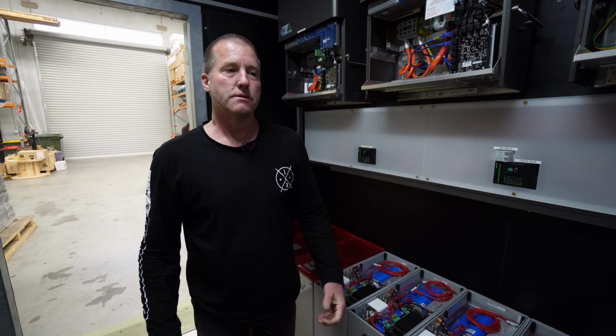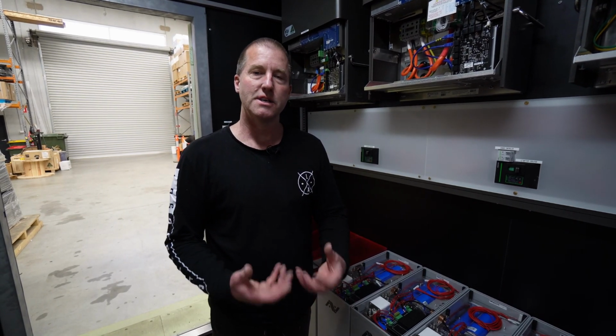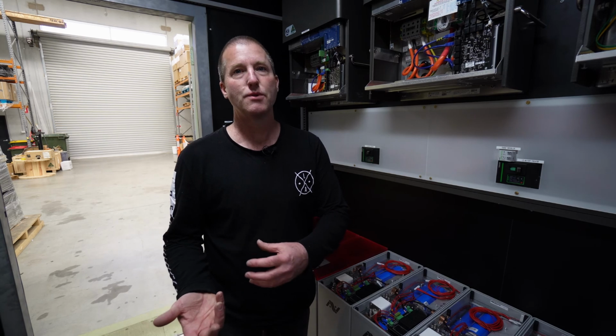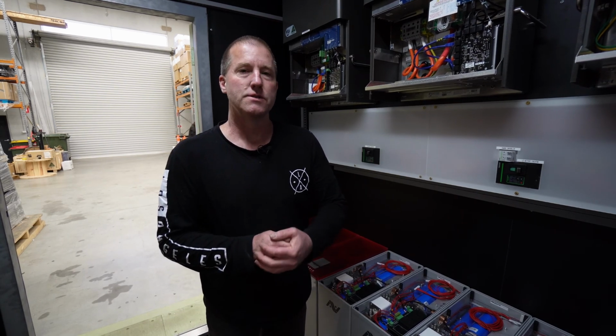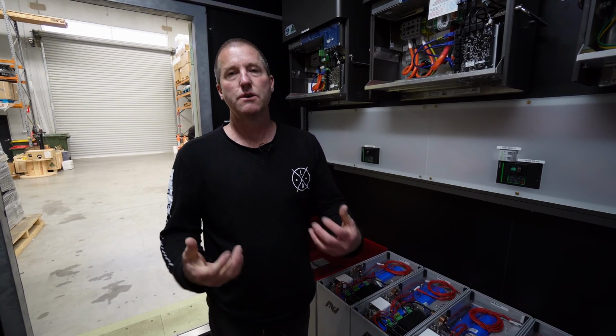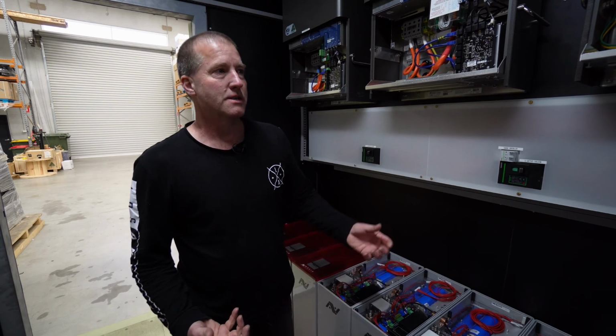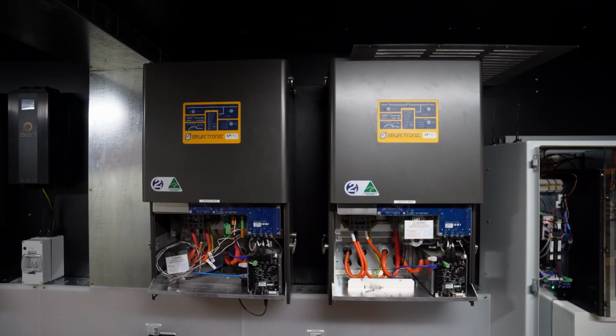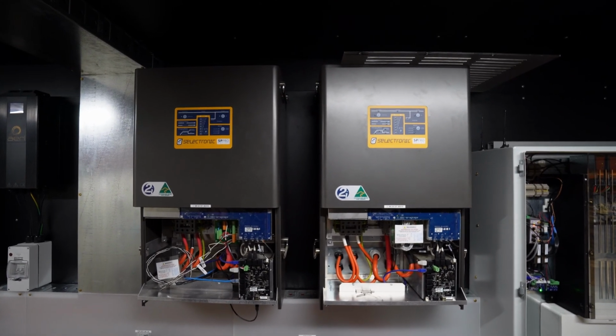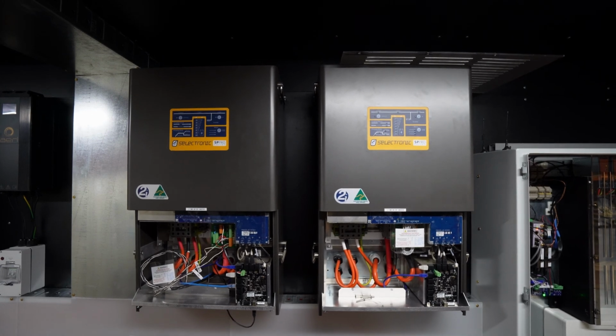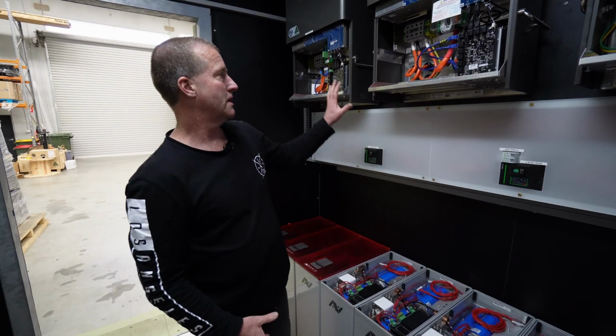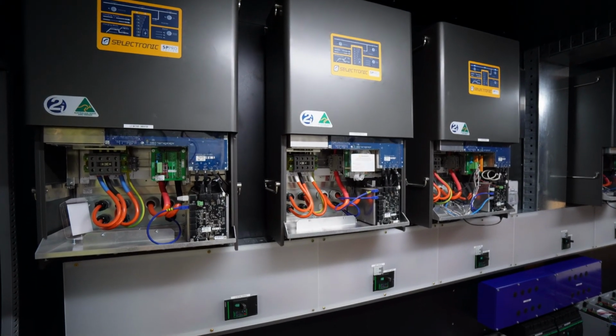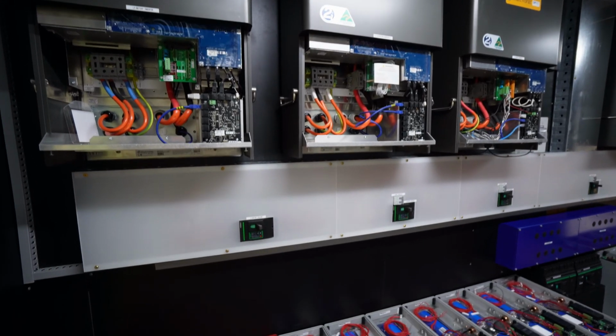So we said, why don't we design a system to bring in the single-phase power and convert it to DC, then produce a three-phase supply for you. That'll also give us the ability to add a lot more solar, because we're off the grid. So we designed a system where we bring in two inverters off the SWER line, produce a DC bus, and then reform three-phase over here. We also have a backup generator for these three phases if we want to run completely off-grid.